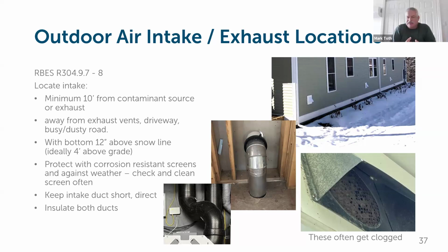The pollen in the air clogs them. If you're mowing the lawn and they're too close to the bottom, they can get grass. In the fall, they can get leaves in them. If they're up high, I've seen a lot of them that are up high and too close to a light. So in the summer, they're acting like a moth vacuum, and they get plugged with moths and all kinds of stuff. So that is another maintenance item, not only inside the house, but outside.